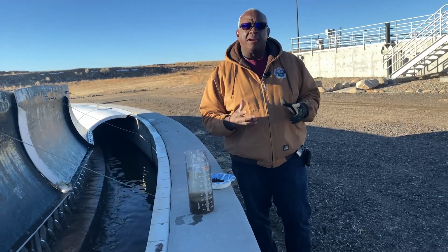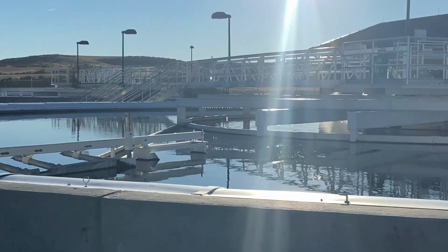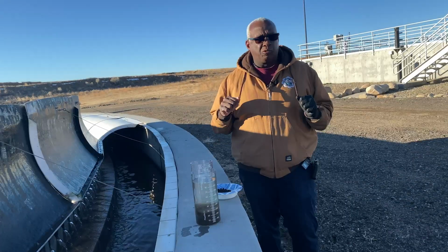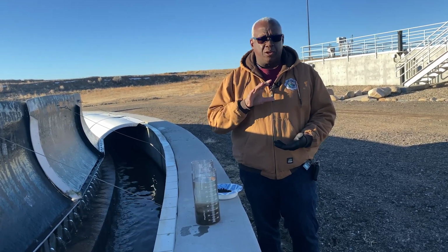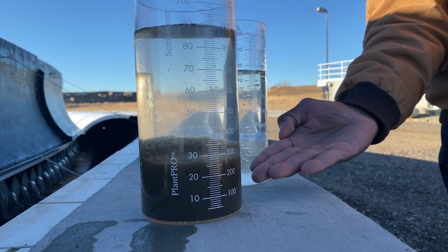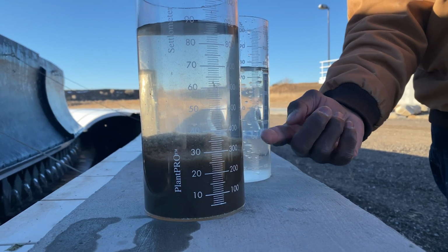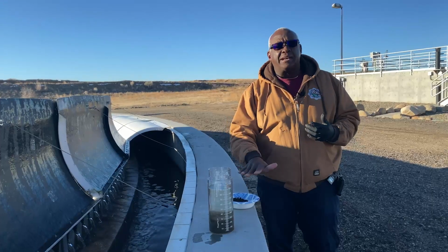After the flow leaves the aeration basin, it comes to the clarifier here. In the clarifier, we actually let gravity do a lot of the work. And gravity helps us separate the solids that are in the flow from the clearer liquid. As you can see in this example, this is the sample we just pulled out of the aeration basin. And the solids are here falling to the bottom as the clear rises to the top. The solids consist of what are now inactive microorganisms that have filled up on the organic material in the waste stream back in the aeration basin. They come over here, they go dormant, and they settle to the bottom.